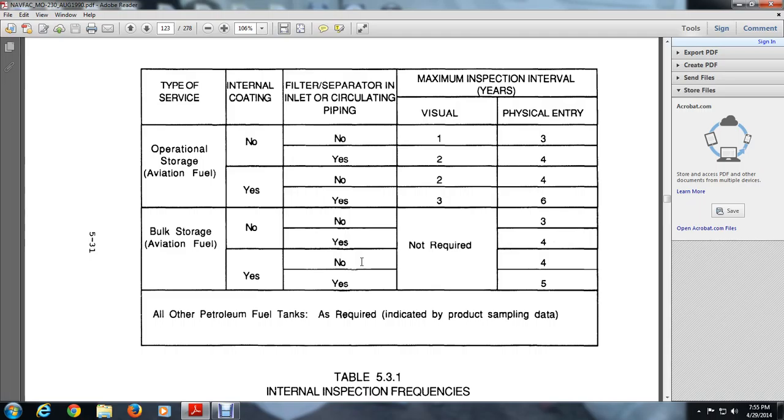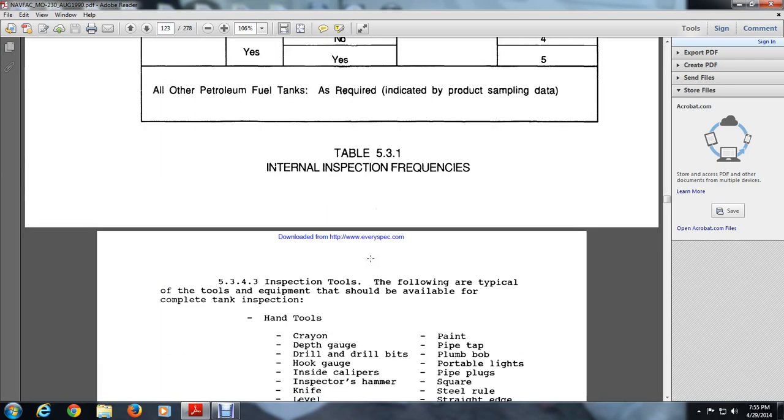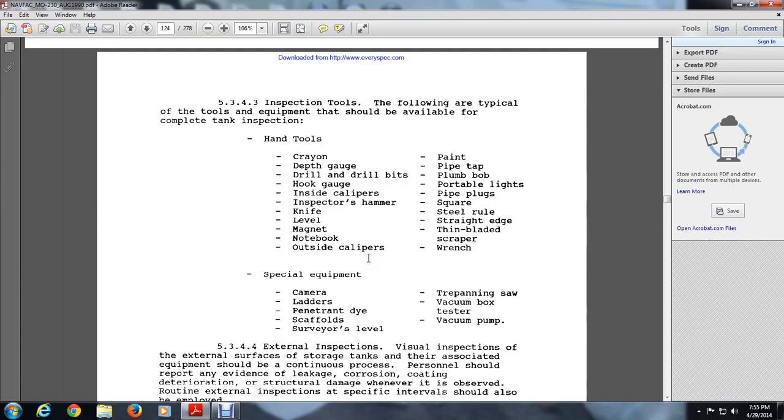5.3.4.2 Safety Precautions. The tank to be internally inspected should be clean, gas-free, and lead-free before inspection begins. All safety precautions including the use of protective clothing and breathing apparatus must be strictly followed. Here is Table 5.3.1 showing internal inspection frequencies. The table covers type of service, internal coating, filter separator in circulating piping, and maximum inspection intervals in years. For operating storage of aviation fuels, intervals range from 1 to 3 years for visual and 3 to 6 years for physical entry depending on coatings and filtration. 5.3.4.3 Inspection Tools. Typical tools for a complete tank inspection include: hand tools, depth gauge, drill bits, hook gauge, inside calipers, inspection hammers, knife, level, magnet, notebook, outside calipers, paint, plumb bob, portable lights, pipe plugs, square, steel rules, straight edge, thin blade scrapers, and wrenches.